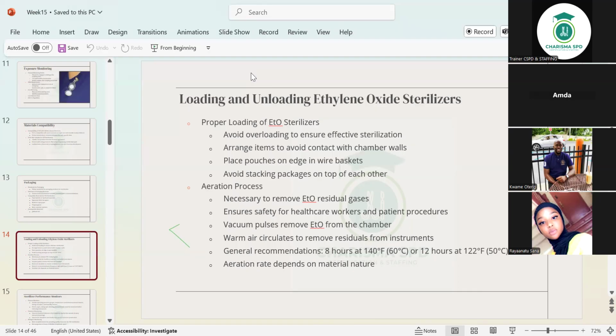This one, I think we didn't say, but we spoke about overloading. If you don't overload, there's no way your instruments are going to touch the walls. But if you overload, then you may force your instruments to touch the inner wall of the chamber. Avoid it. Make sure your instruments don't touch the inner walls. Some sterilizers have been designed such that when you load the items, they're not going to touch the walls anyway, because there are certain points that they will touch and certain points they will not touch.